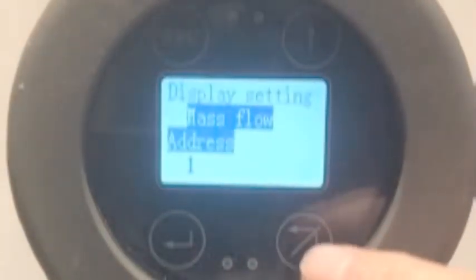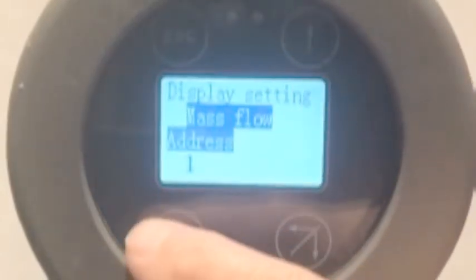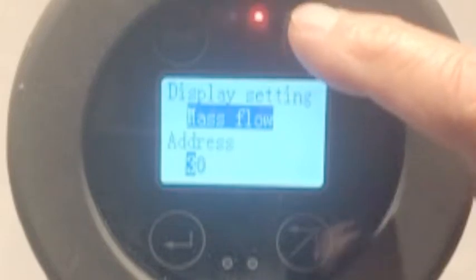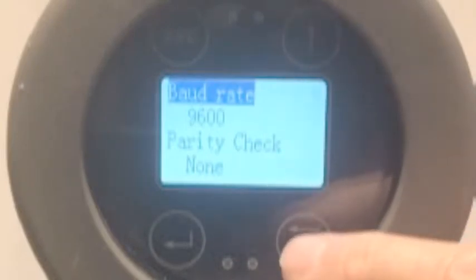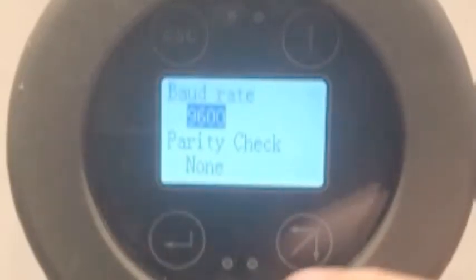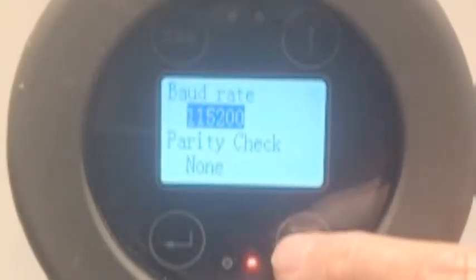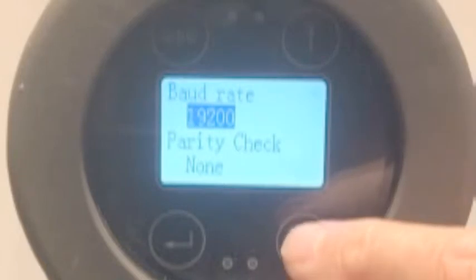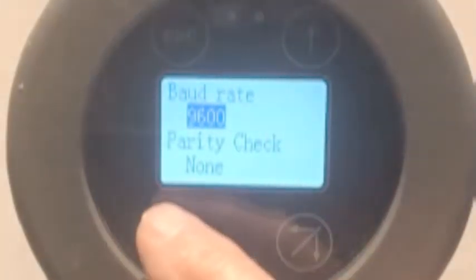The next one is the Modbus address — the Modbus RTU address. It's set to 1 here. I could enter and change it to whatever I want, but I'm going to go back to 1 because that's what I'll display and show you. Baud rate is 9600. You may want quicker than that — 19.2, 48, 24, or 115.2 are available. I'm going to leave it at 9600 because that's what I have in the manual for folks.